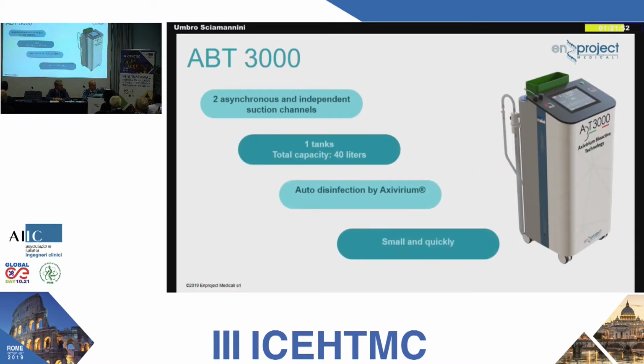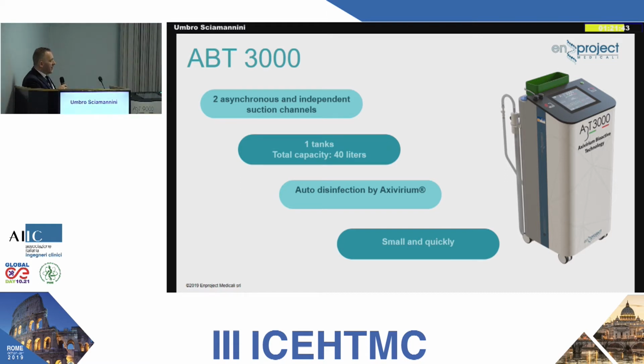The ABT 3000, the smaller one, has only 1 tank for a total of 40 liters, and 2 asynchronous and independent suction channels. It has auto disinfection by Axivirium, not thermal because there isn't a heater, but if connected to the hospital's hot water, you can also achieve thermal disinfection. It's small and quick for the patient's room, where its compact size helps the staff with daily use.